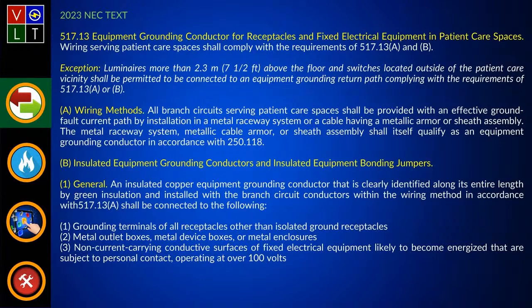And so what they want to do is make sure that in these patient care areas they have the best possible equipment grounding path, regardless of whether it's the equipment grounding conductor or a bonding conductor. They both act together to ensure an effective ground fault current path. Sure. And I really like this slide, James. That's a good one.